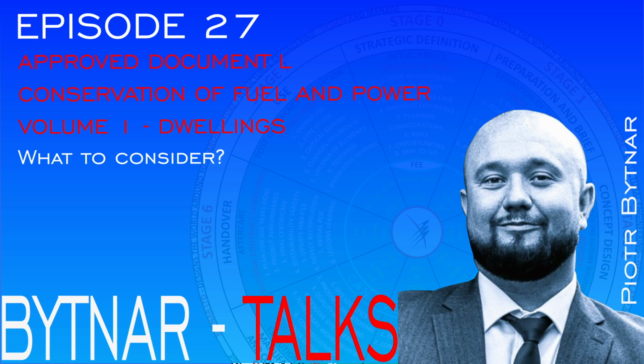Combi boilers should be able to modulate down their heat output to the level generally required by the dwelling. New wet heating systems need to be sized to meet the requirement of low temperature heating, so flow temperatures at 55 degrees Celsius maximum. That is also applicable to entirely new systems in existing dwellings. This will not always be feasible, and whenever it is not, we need to size the system so it runs at the minimum that becomes feasible.